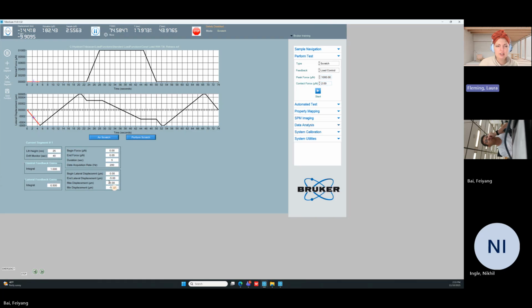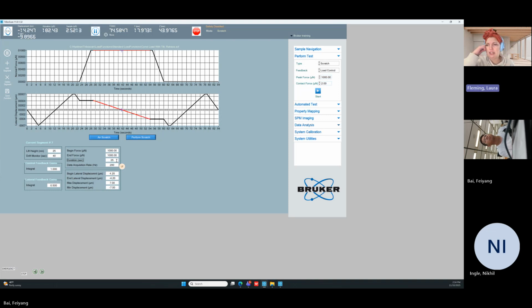Down here are your global settings that can change the scratch length. Right now the scratch length is 6 microns. I change the max displacement to 7 and the min displacement to -7. It updated these two items, and then it made this longer proportionally. So you can update the entire load function to change the length of the scratch. And of course, you can also change the time, the duration. You can make that very long if you want to scratch slowly for some reason, if that's important for your sample, or very quickly.